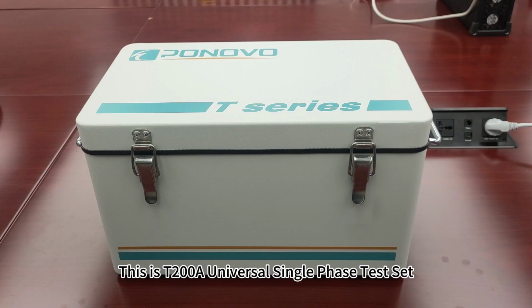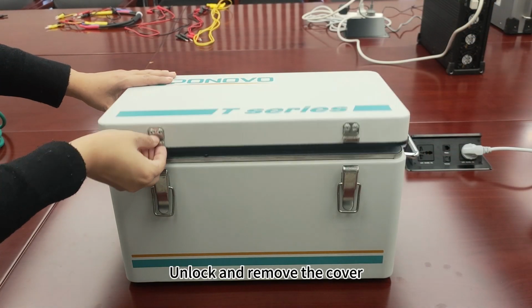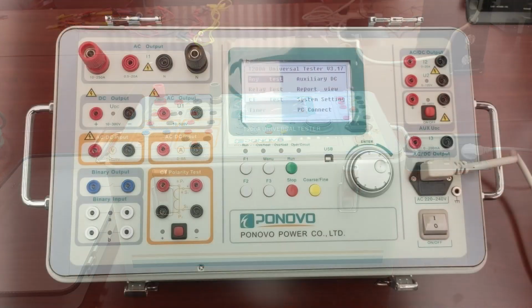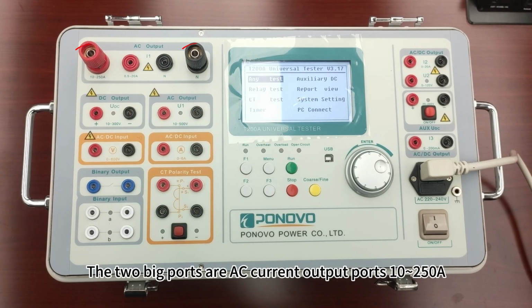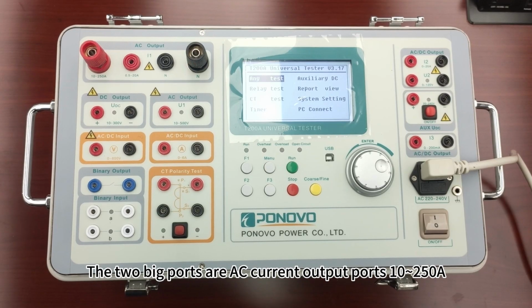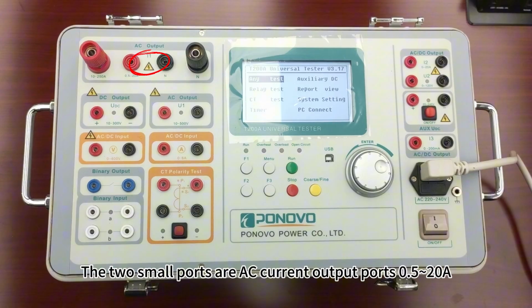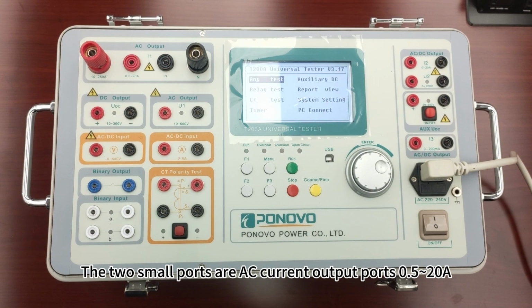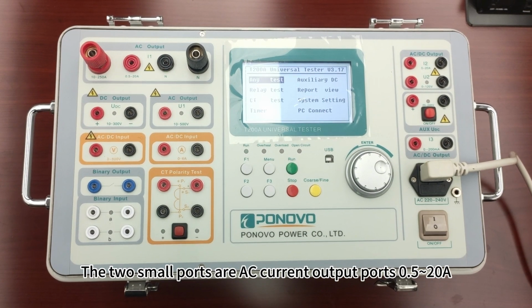This is T200A universal single-phase test set. Unlock and remove the cover. This is top panel. The two big ports are AC current output ports from 10 amperes to 250 amperes. The two small ports are AC current output ports from 0.5 ampere to 20 amperes.